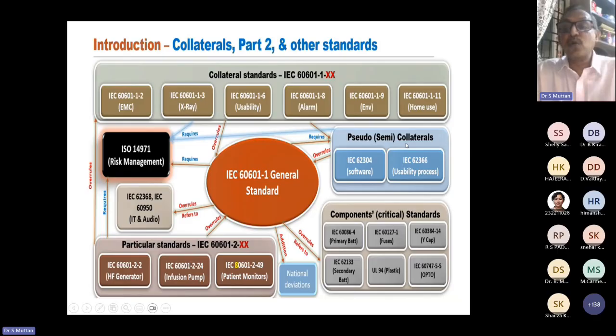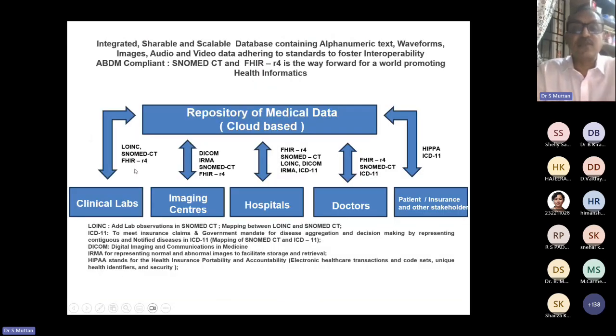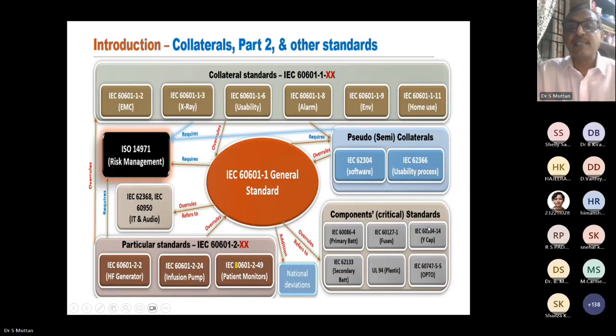Then you have pseudo collaterals, IEC 62304, all the software. These are all complete software platform. So whatever software you write, you have to get this standard. IEC 62304 is the software standard. So you have to get a certificate from the agency who will certify that your software is in compliance with it. It's nothing but the life cycle of a program. You are very comfortable with the SDLC, we call it system development life cycle. That is what IEC 62304 is, and then usability, because it should be user friendly.